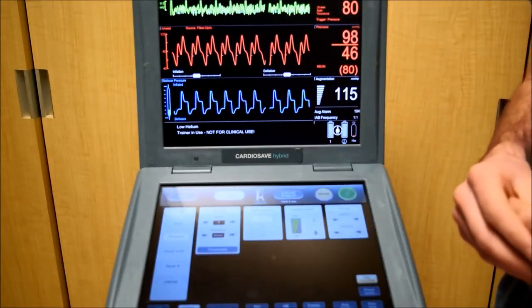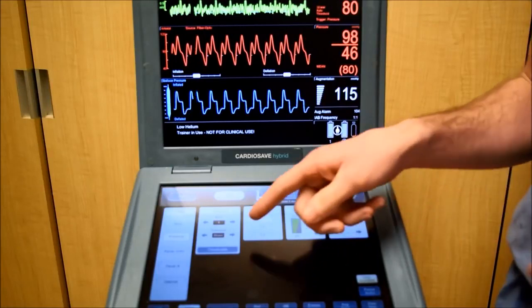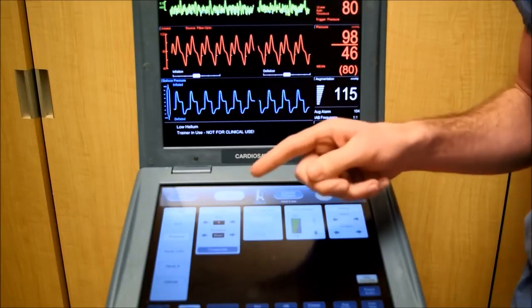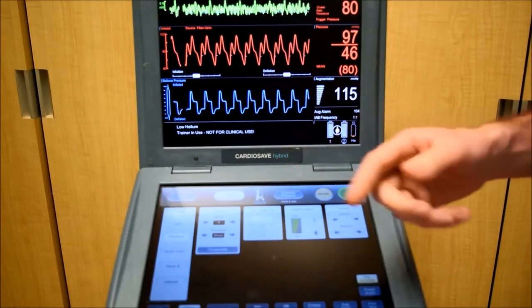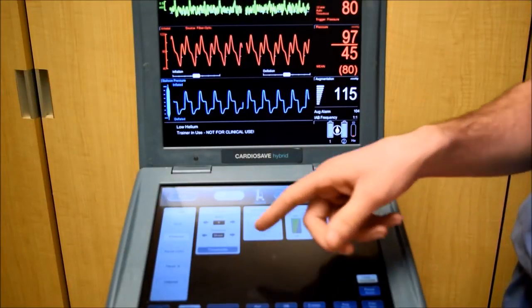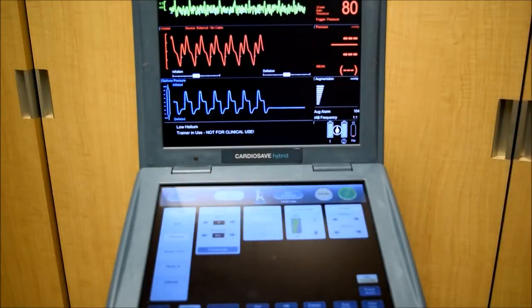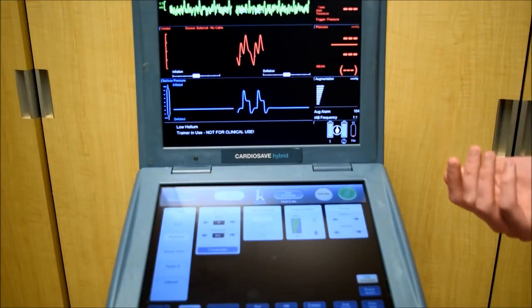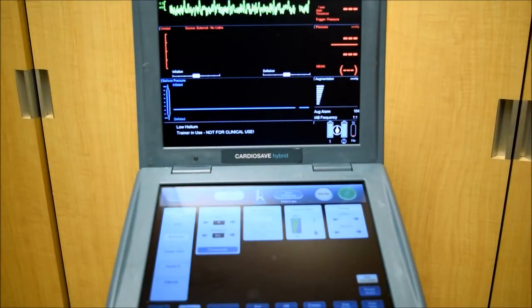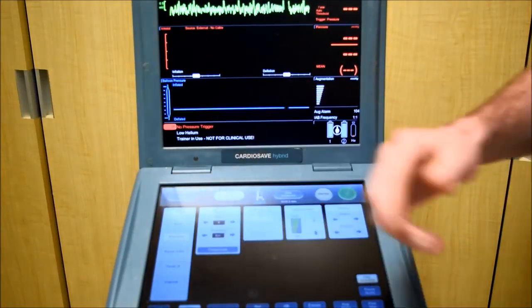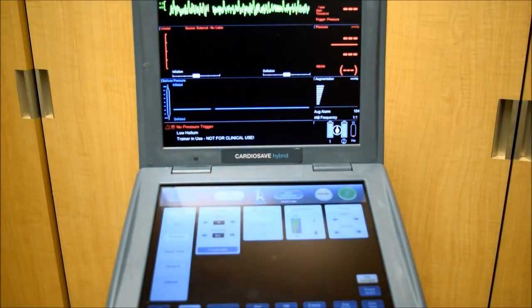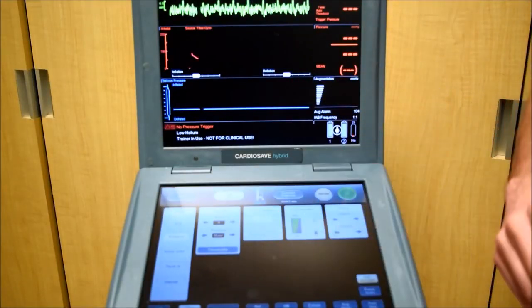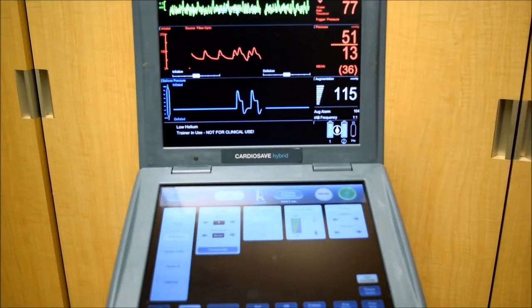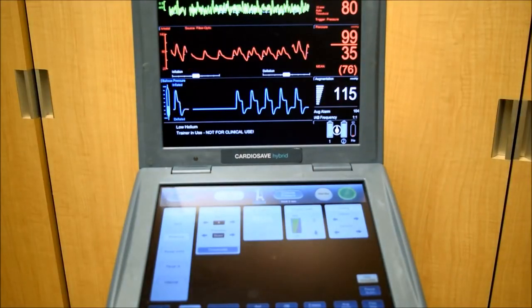The pressure source can also be slaved, and to adjust this, you can either have direct. This means the pressure reading is coming from the tip of the balloon catheter, or if it's external, that means if you're slaving from the monitor, you can also use that. However, I'm currently not slaving, so we do not get a pressure signal. An alarm appears, no pressure trigger. You can either switch back to an ECG trigger or switch back to your direct pressure source. Now the balloon will resume normally.